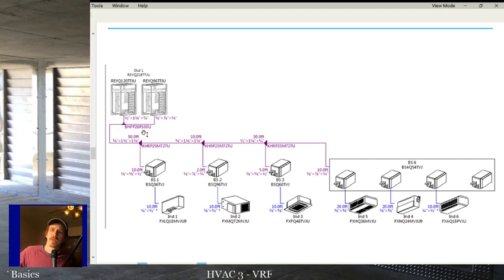You will connect the outdoor units. The outdoor unit T kits sometimes look more like T's than the indoor unit Y branch kits, but they'll all connect together, and one outdoor unit will be the primary one.